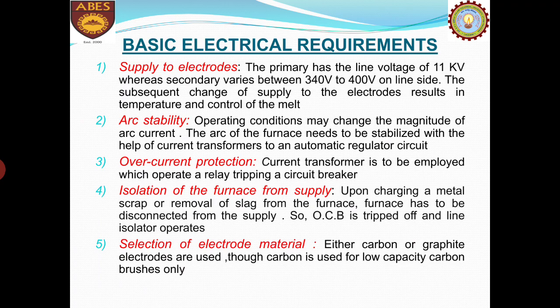So for this purpose, the furnace transformer has a high reactance of 35% and multiple tappings on the secondary. The primary line voltage is approximately in the range of 11 kilovolts, while the secondary varies between 340 to 400 volts on the line side. The bus bars supplied by this multiple tap secondary are connected through flexible cables capable of carrying hundreds to thousands of amperes of current, and it will obviously depend upon the melting capacity of the furnace. The subsequent change of supply to the electrodes results in the temperature control of the charge or the melt which we are going to work upon.